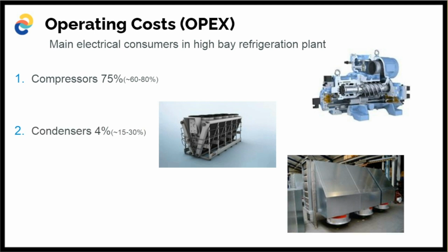But the air coolers are also much higher than you would expect. Big air coolers, lots of air, lots of fans. Let's say for one of the coolers like this, you have a couple of fans. They are 7.5 kilowatts each, so on an average one, you are looking at between 150 kilowatts and 200 kilowatts of electrical power for all the coolers in a high bay. So that's quite significant if you look at it on a yearly basis.